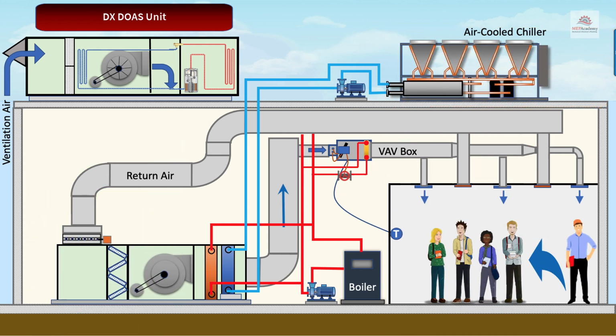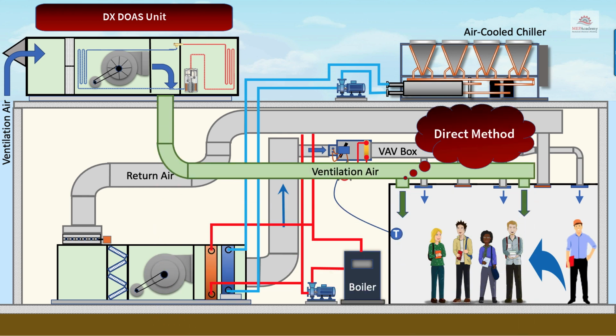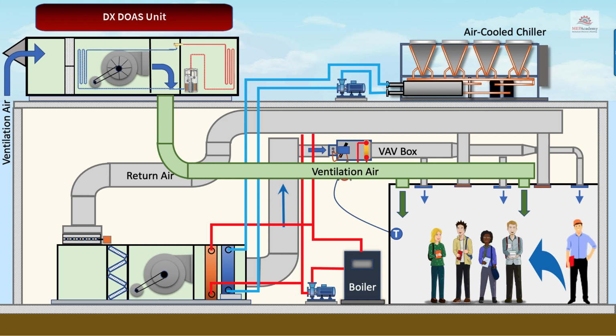Now we'll remove the indirect ventilation ductwork and connect the DOAS ventilation air directly to the space without going through the air handler. One of the issues that the use of a DOAS resolves better than a recirculating VAV system is that of delivering the proper amount of ventilation air to each space or zone. A VAV air handler can often overventilate a highly populated space.